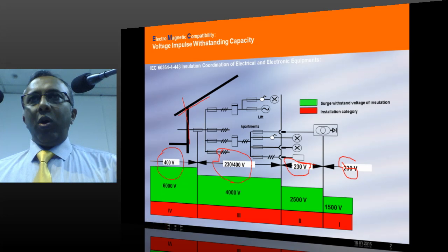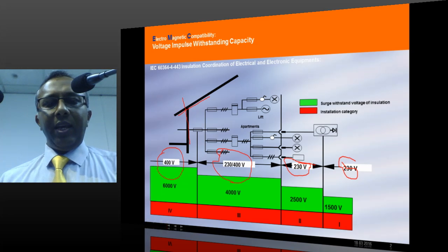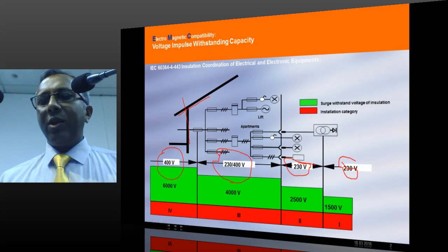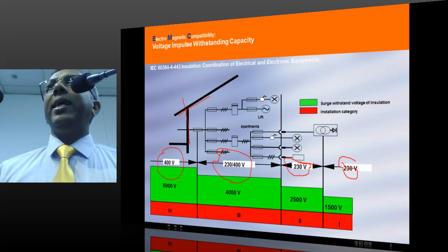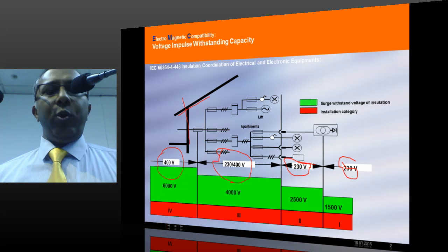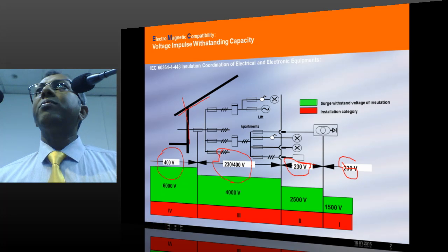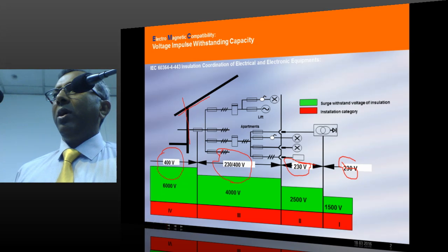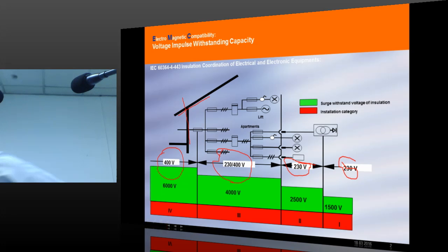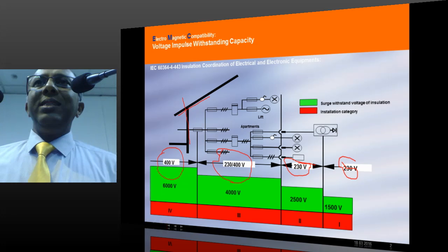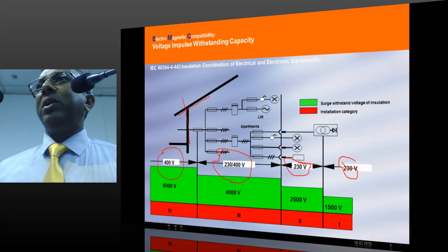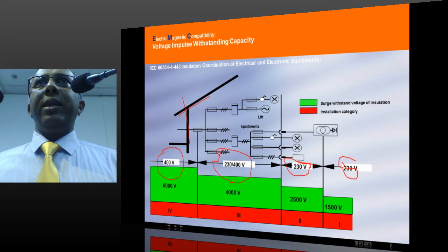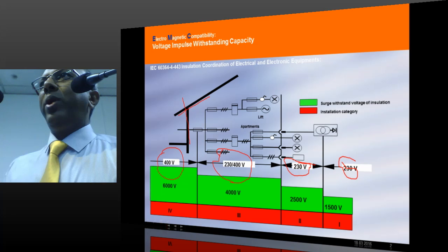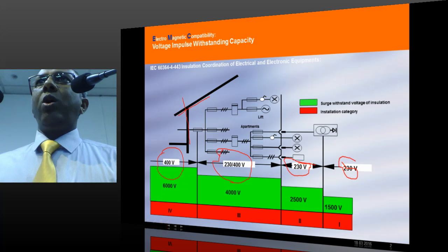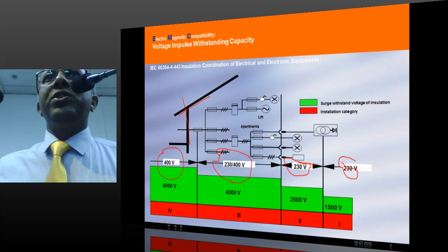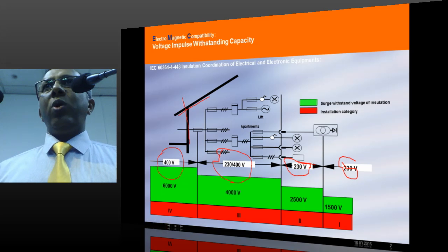Numbers 4, 3, 2, 1: 6 kV, 4 kV, 2.5 kV and 1.5 kV. These are called installation categories of low voltage electrical equipment operating with 400 or 230 volt. Installation category means with respect to voltage impulse withstanding capacity. What is voltage impulse withstanding capacity? Every electrical device, after manufacturing, the manufacturer should test the voltage impulse or the insulation voltage of the equipment, and he has to declare how much insulation voltage continuously, impulse voltage, this particular device can withstand.